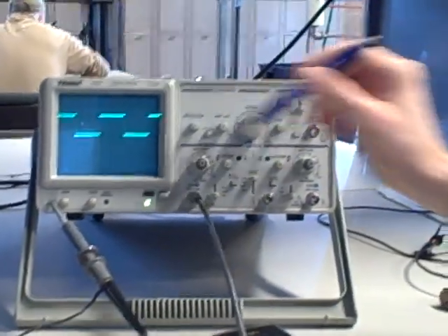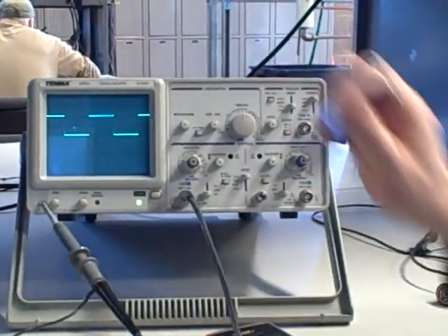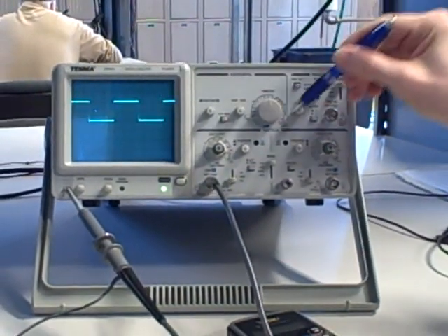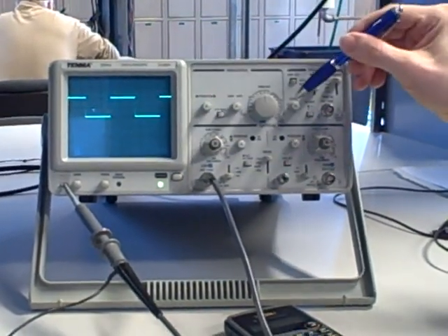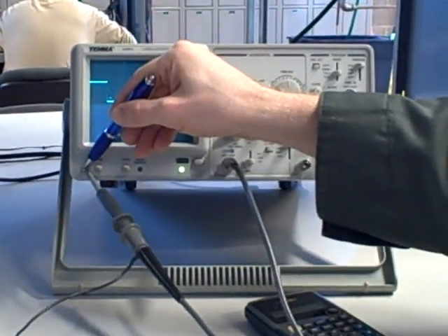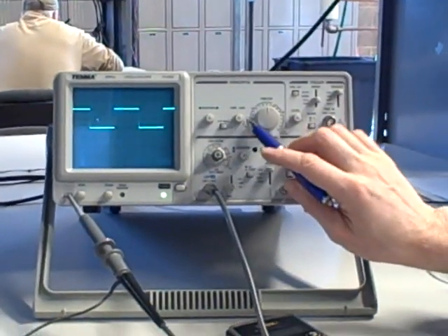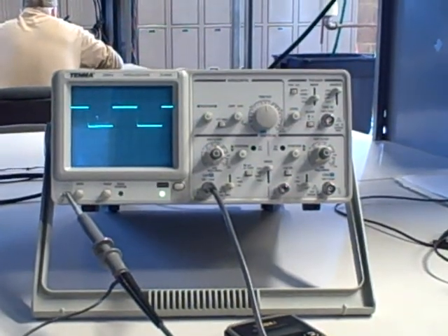So this is a self-check. So if you hook the scope up to its own signal, I should say, and things don't work out right, either you have a calibration issue here or maybe the signal generator internally has a calibration issue, but one of them is off, and the scope needs servicing or you need to very carefully check and make sure you didn't do something like that.